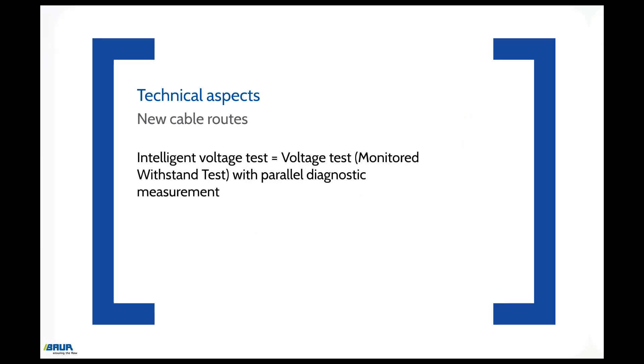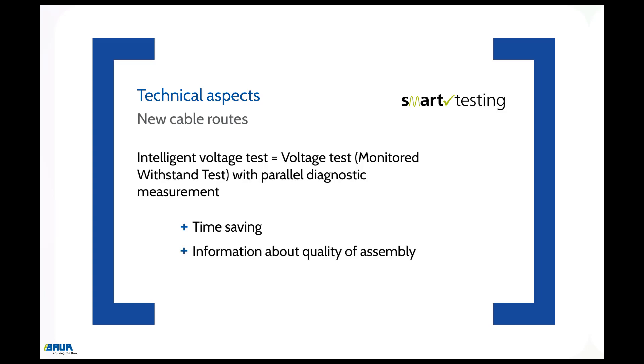Cable diagnostics is widely used in the acceptance testing of new cable routes. More and more power supply companies are replacing the simple voltage test with intelligent voltage testing called smart testing. This means that in the monitored withstand test, voltage testing and diagnostic measurement are performed at the same time. This saves time and supplies valuable information for asset management, giving users a very clear idea of the quality of the assembly work. Assembly errors are thus highlighted at an early stage and can be eliminated during the warranty period.